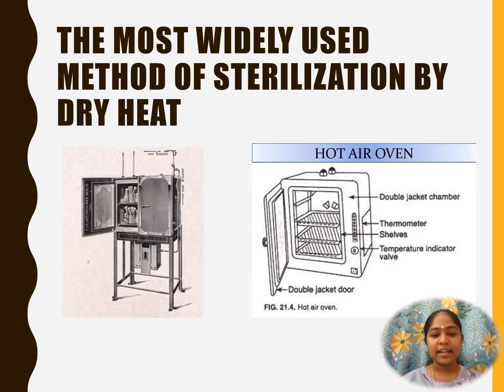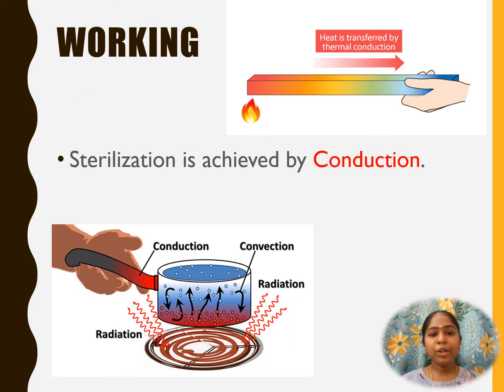Articles to be sterilized are exposed to high temperature in an electrically heated oven. Since air is a poor conductor of heat, even distribution of heat throughout the chamber is achieved by a fan. Coming to the working of the hot air oven, sterilization here is achieved by conduction. The heat is absorbed by the surface of the item to be sterilized, which then penetrates to the center until the entire item reaches the desired temperature.